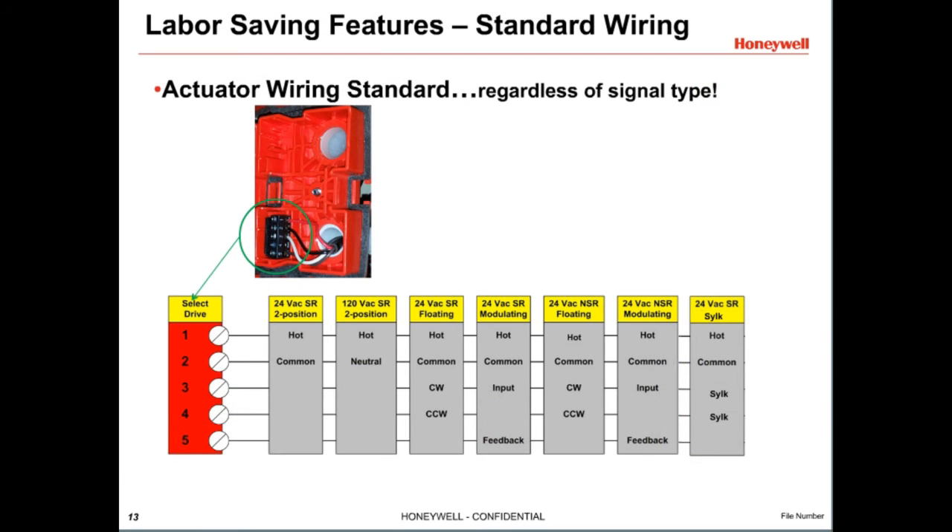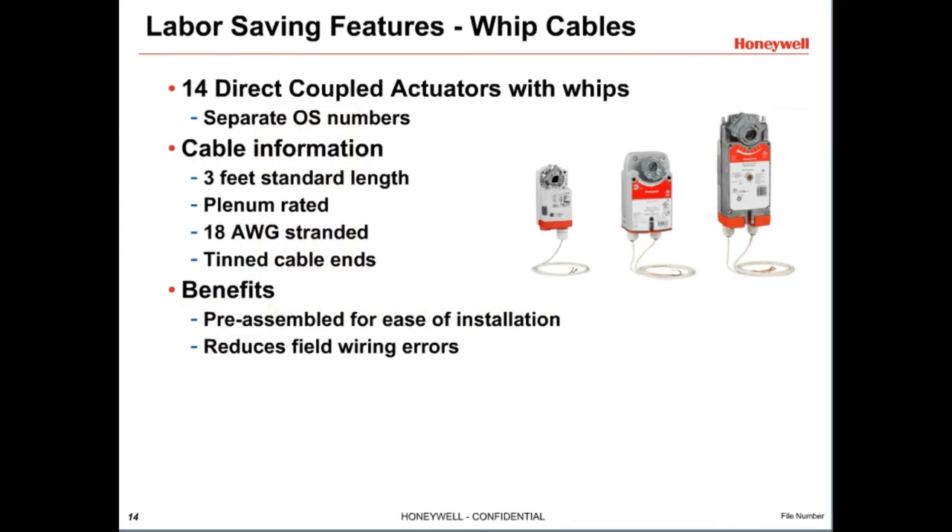To make wiring simple and easy to learn, all Honeywell DCAs follow a wiring standard. Terminal pin 1 is always hot, and pin 2 is the common or neutral. Pins 3 and 4 are the control signals such as floating, modulating, or Sylk bus. Pin 5 is used for feedback on modulating models. To simplify wiring even more, you can order Honeywell DCAs with a 3-foot cable or whip. The whip is pre-wired to the actuator, so you only have to wire it to the controller, reducing wiring time and the risk of miswiring.